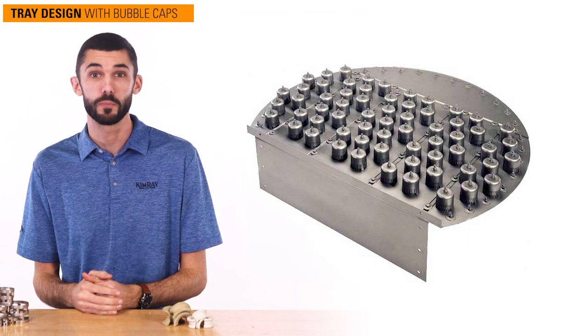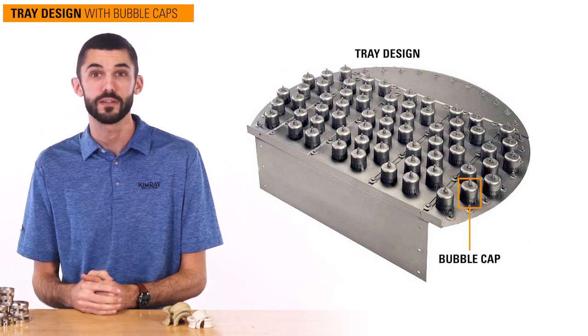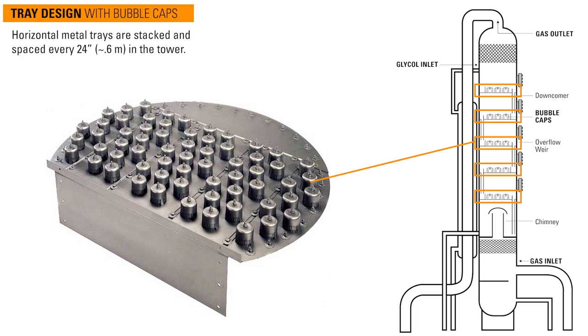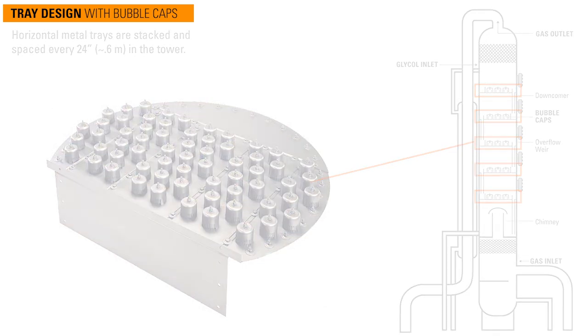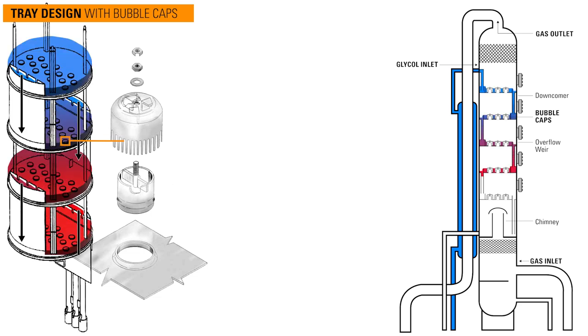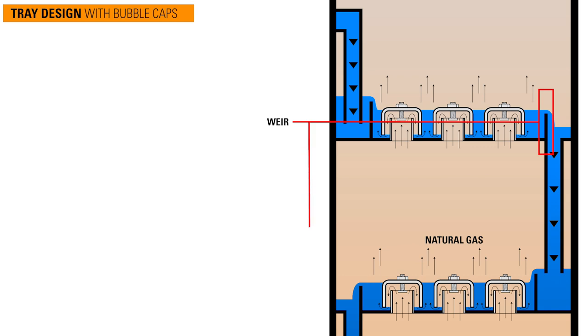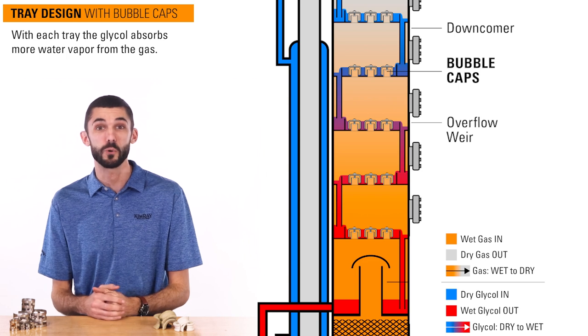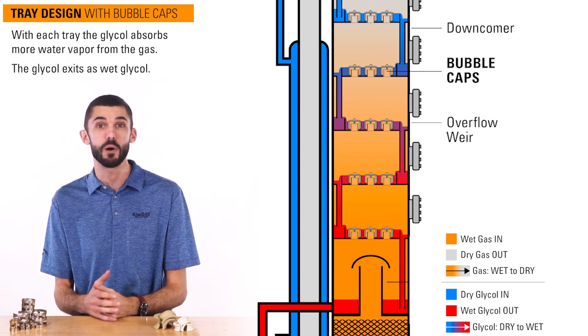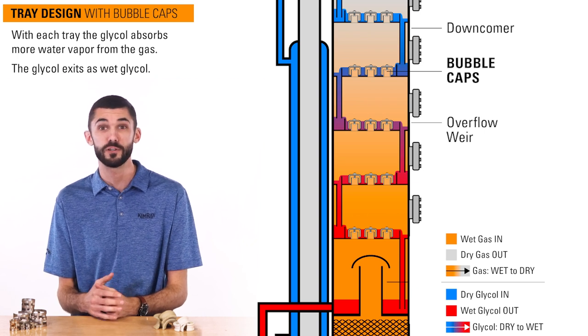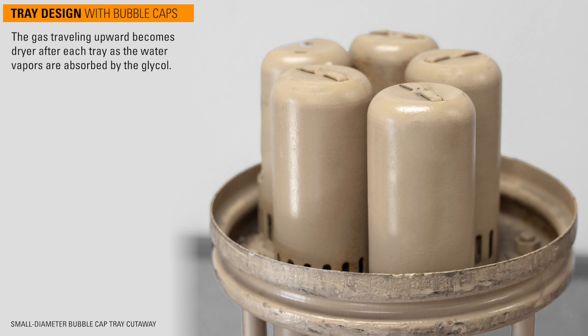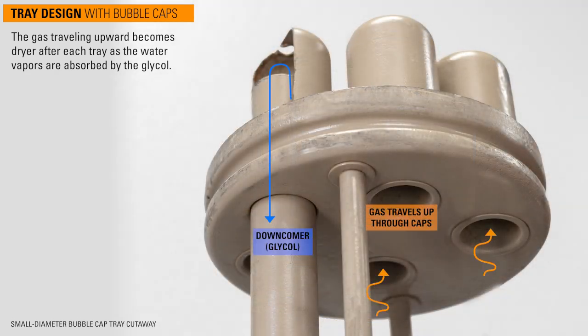The third and most common type of absorber tower is a tray design with bubble caps. In this design, horizontal metal trays are stacked and spaced every 24 inches in the tower. Dry glycol enters the tower at the top and pours over the bubble caps. The gas moves up from under them and seeps through the holes in the caps. A level of glycol is held on each tray by a weir before it travels through a downcomer to the next tray. With each tray, the glycol absorbs more water vapor from the gas. When the glycol exits the bottom of the tower, it is saturated with water and referred to as wet glycol. The gas traveling upward becomes drier after each tray as the water vapors are absorbed by the glycol.